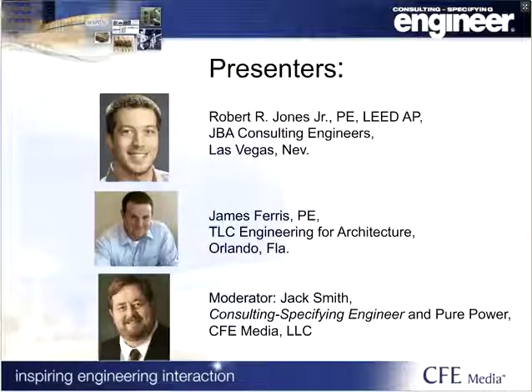I think I might pass this one to Jim if you could. Sure. So the rating of the generator, you would certainly get a more robust generator if you're calling for a continuous rated generator than a standby rated generator. But let's say you want a 1500 kW generator: at standby it's going to be X size, and at continuous it's actually a bigger generator. That continuous generator that you're calling for at 1500 kW would actually be equivalent to, let's just say, 1800 kW standby. So you are getting a little bit more robust unit, but you are also getting the space and paying the money for it.